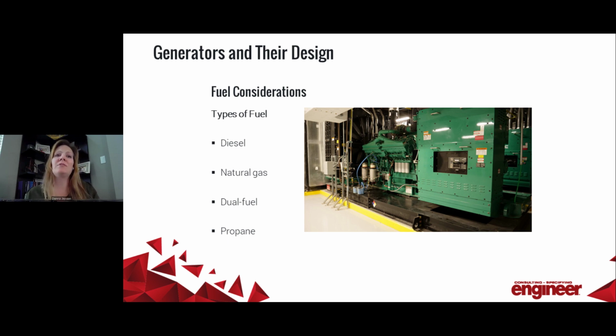They also don't really respond well to 100% block loading, their transient response time is definitely not as efficient as diesel. And they're typically physically larger. They also typically take longer to come up to speed. So when you're dealing with level 1 systems and large engines, you don't really have a guarantee that they will be up and running in the required 10 seconds.